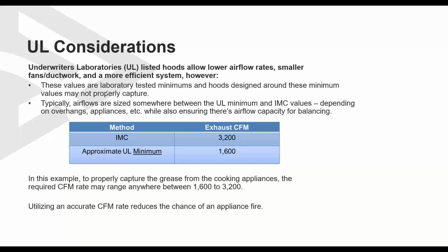The main reason behind that is because these values are lab tested minimums, and hoods designed around these minimum values may not properly capture. Typically, airflow is sized somewhere between the UL minimum and IMC values, depending on overhangs, appliances, etc., while also ensuring there's airflow capacity for balancing. In this example, to properly capture the grease from the cooking appliances, the required CFM rate may range anywhere between 1,600 to 3,200 CFM total. Utilizing an accurate CFM rate reduces the chance of an appliance fire.